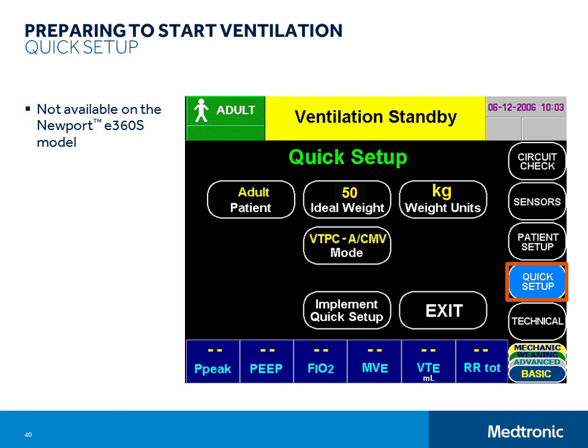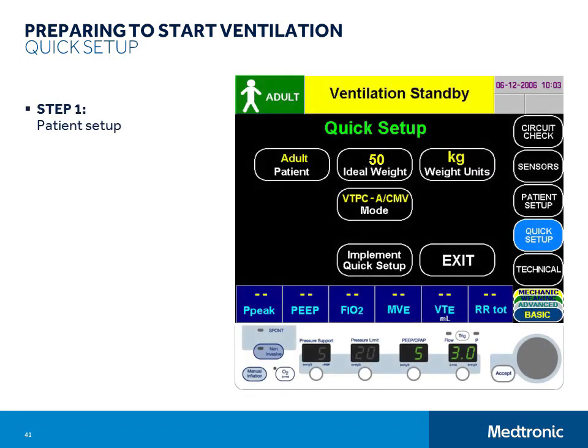We are covering Quick Setup at a point in our setup process when gases are already connected to the e360. But you can power the ventilator on and activate the Quick Setup without any gases connected to the ventilator as well. Remember that all ventilator settings except the non-invasive setting are stored in memory when the unit is powered down. The first step in the Quick Setup process is to confirm that the settings for patient type, ideal weight, and weight units are correct, and if not, to correct them and then press Accept to confirm the changes.